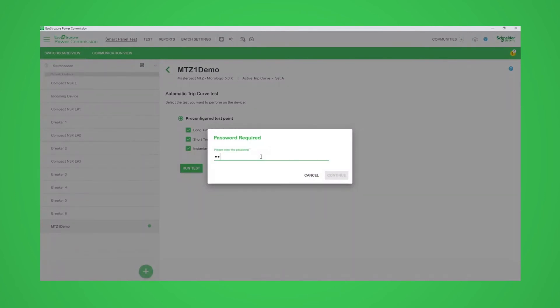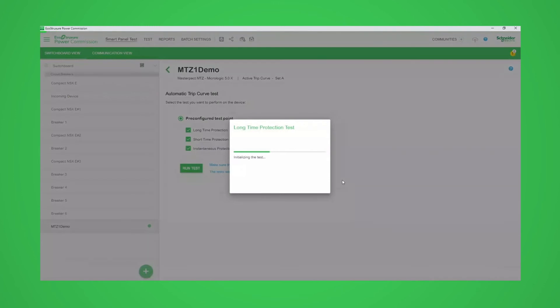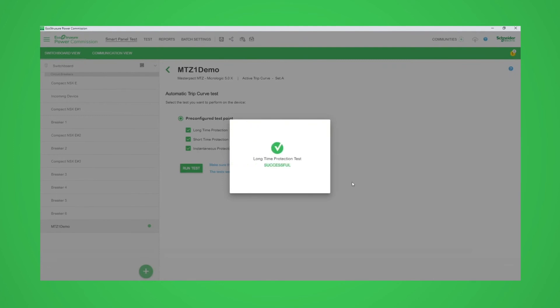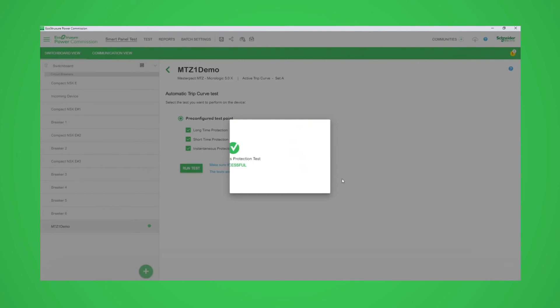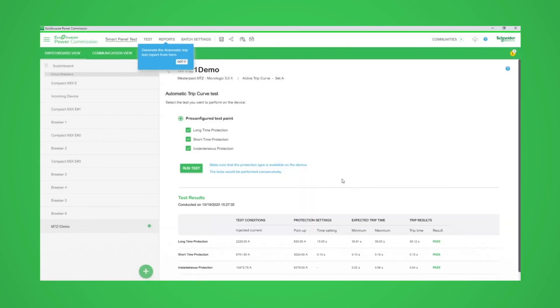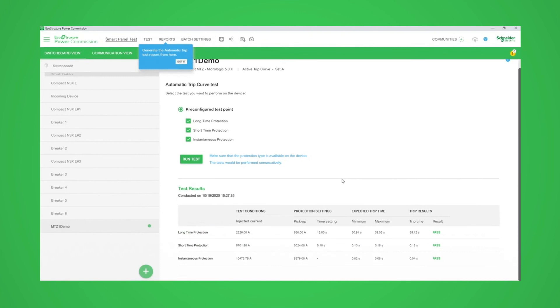Enter the admin passcode for the trip unit and click Continue to run the tests. Depending upon your protection setting, this may take a little while. Follow the on-screen instructions and reset and close the breaker as necessary. When all tests have finished running, the test results will appear at the bottom of the testing page.